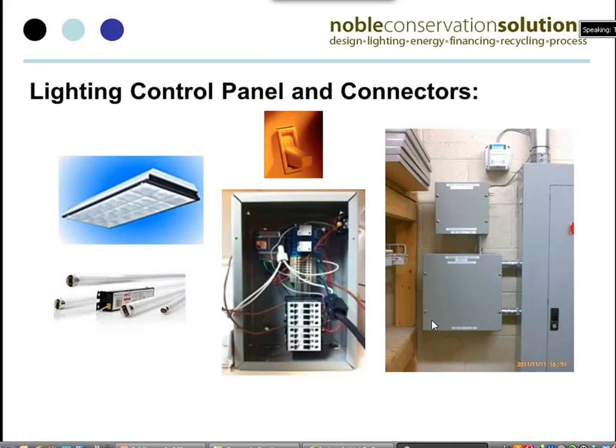We also control lighting. In addition to the rooftop units, we put in very sophisticated switches, so we can help our clients turn the lights off when they're no longer in their stores. We've had situations where we've come into stores and found that they run their heating and cooling at the same level 24 hours a day, 365 days a year, and they happen to be in an environment in Texas that gets extremely hot. It can be 110 outside, and they come to the back office that nobody's in the middle of the night at 68 degrees, and they're running cooling to maintain that.